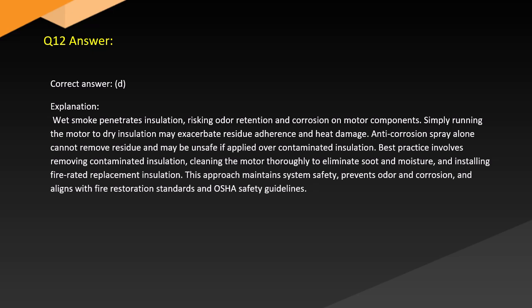Answer. Correct answer. D. Explanation. Wet smoke penetrates insulation, risking odor retention and corrosion on motor components. Simply running the motor to dry insulation may exacerbate residue adherence and heat damage. Anti-corrosion spray alone cannot remove residue and may be unsafe if applied over contaminated insulation. Best practice involves removing contaminated insulation, cleaning the motor thoroughly to eliminate soot and moisture, and installing fire-rated replacement insulation. This approach maintains system safety, prevents odor and corrosion, and aligns with fire restoration standards and OSHA safety guidelines.